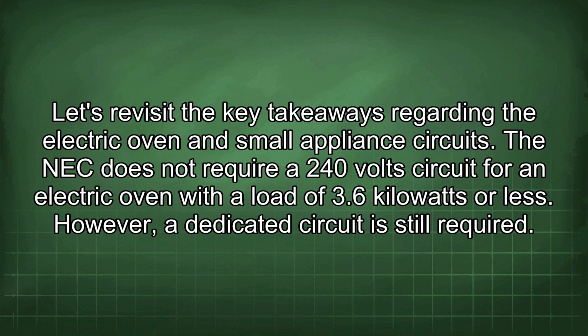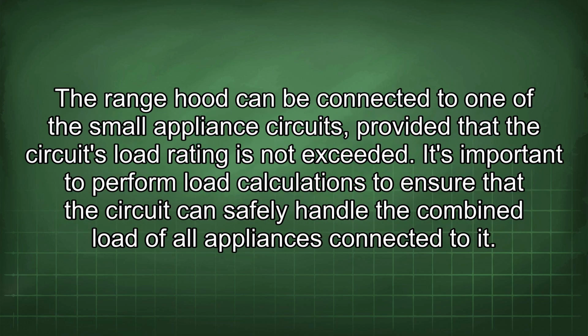Let's revisit the key takeaways regarding the electric oven and small appliance circuits. The NEC does not require a 240 volt circuit for an electric oven with a load of 3.6 kilowatts or less. However, a dedicated circuit is still required. The range hood can be connected to one of the small appliance circuits, provided that the circuit's load rating is not exceeded. It's important to perform load calculations to ensure that the circuit can safely handle the combined load of all appliances connected to it.